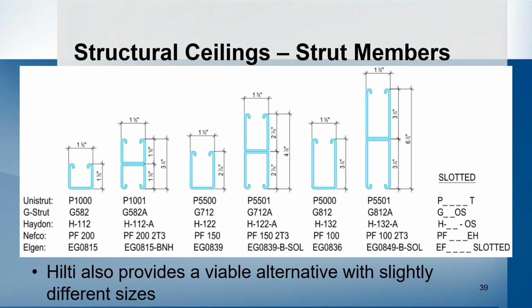So these are a number of different manufacturers that we see here in our market. There's Unistrut, kind of the band-aid of strut. They're just pretty much the generic. And then there's a number of others that follow the same dimensions that Unistrut has, but again, they have different capacities listed for their specific strut. Also the nomenclatures are kind of all over the map here, but the typical base strut is going to be 1 5/8 by 1 5/8. Then, as I mentioned, they have the welded back-to-back. Then it goes a little bit deeper to 2 7/16. They do that back-to-back, and then 3 1/4 with the 3 1/4 back-to-back.